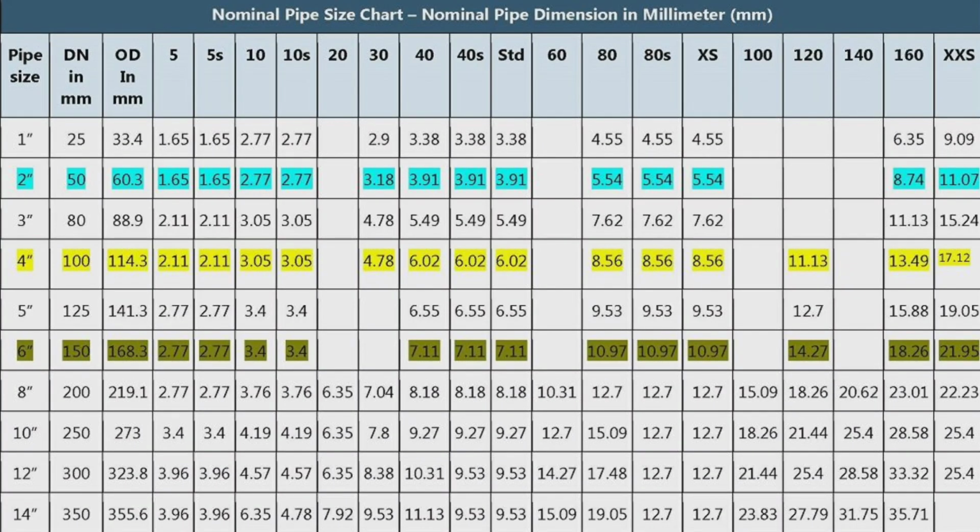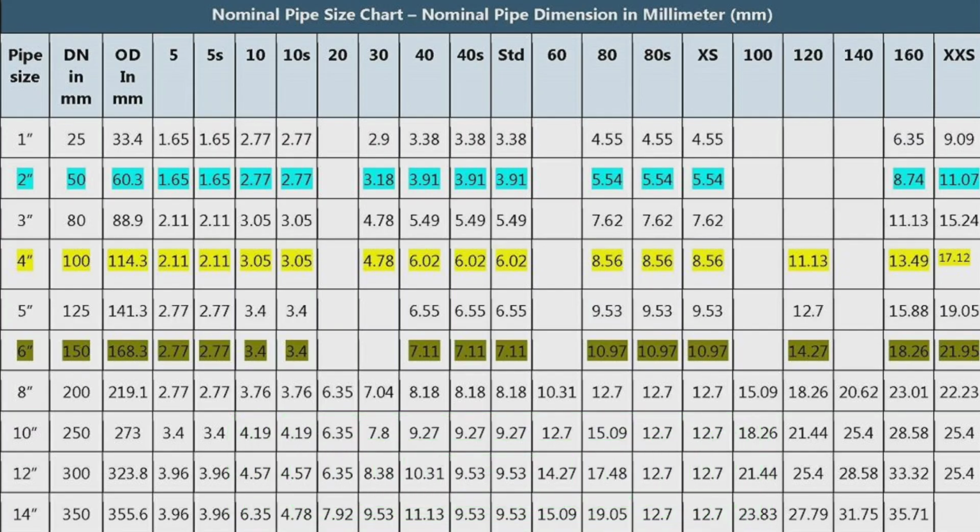What does pipe schedule mean? Two non-dimensional numbers, pipe diameter and wall thickness, are used to identify certain pipes, as measured in the schedule, SCH. Pipe schedule, SCH, is the term used to define a pipe's wall thickness. Pipe schedule number is the standard method to define the thickness of the pipes used in pipe fabrication. Differing schedules can result in different wall thicknesses in two pipes of the same diameter. Therefore, if someone is choosing a pipe for a high-pressure application, they will choose a higher number, which indicates a greater wall thickness.